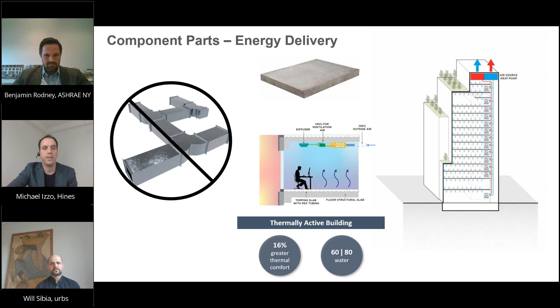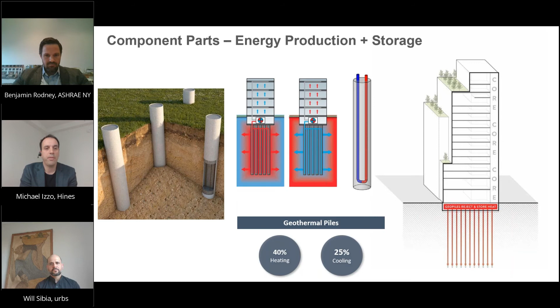Then lastly, but definitely not least, we were driving piles 150 feet, about 100 to 150 feet down to bedrock. So we took the opportunity to put tubing within those piles and use it as a geothermal system. And before going to the Nordics, I always thought about it as free energy, but the reality is that it's also storage. So not only is it energy you can take up from the ground, but it's also energy you can store in the ground to be used at a later date. This provides about 40% heating and 25% cooling to the building.